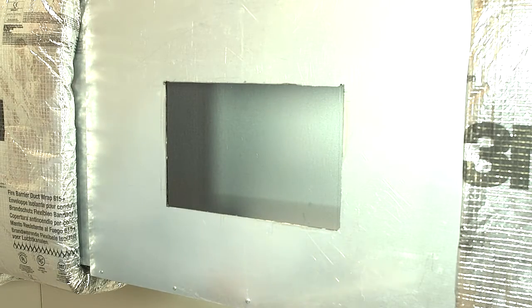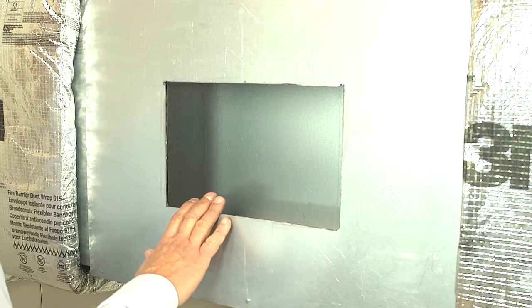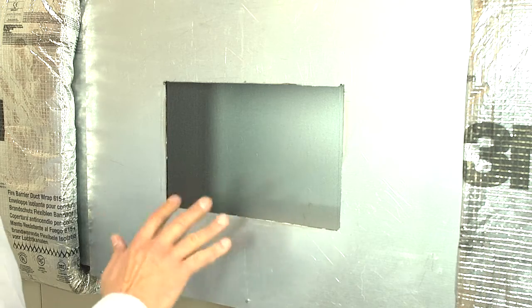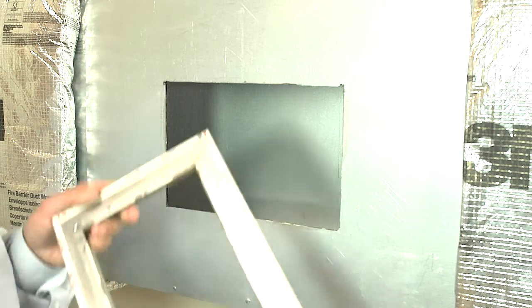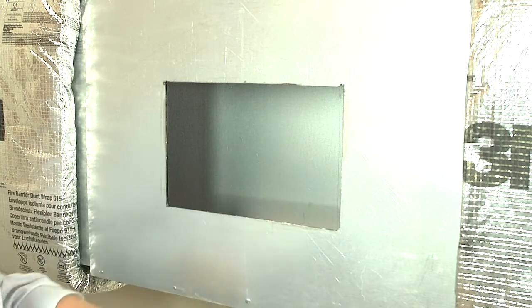All right, we are going to install a 6x10 easy access door. So in order to do that, we cut the hole in the duct at 7 inches by 11, so one inch extra from the size of the door. I'm now going to take the base mounting plate and take the relief paper off.